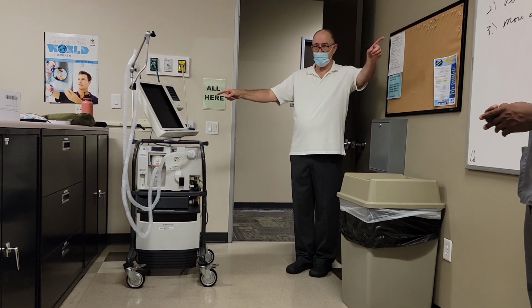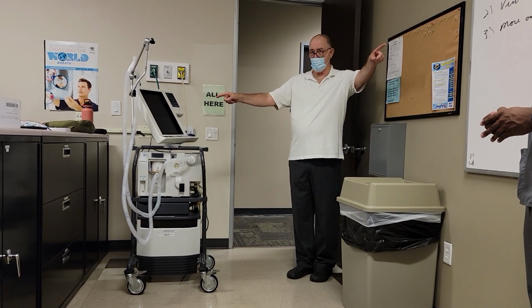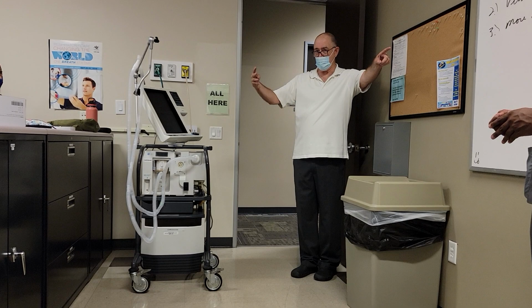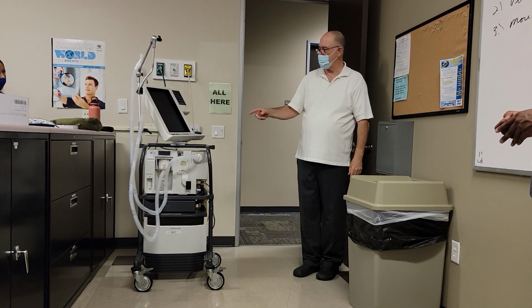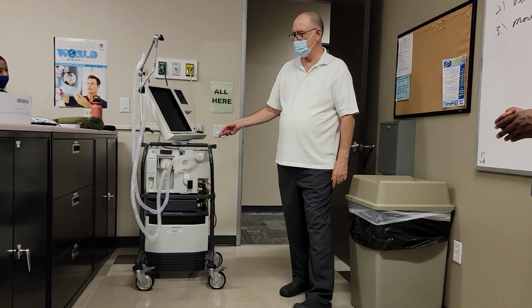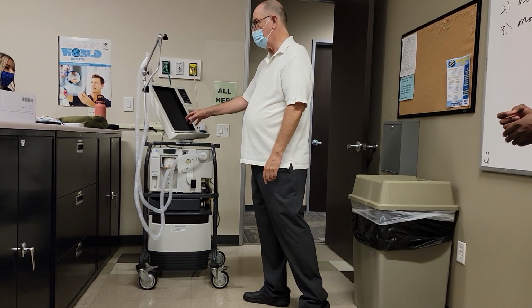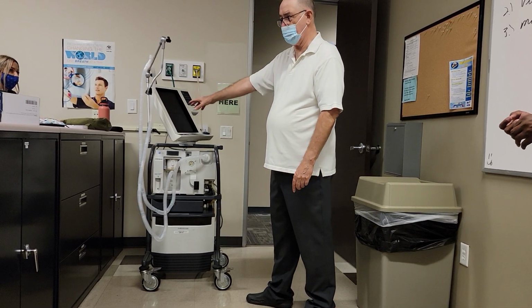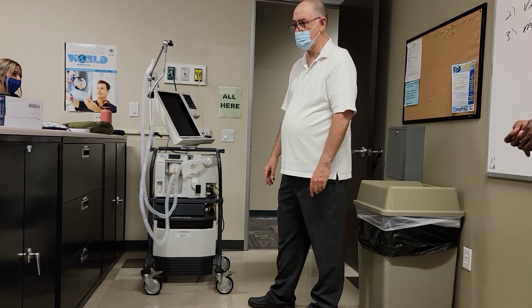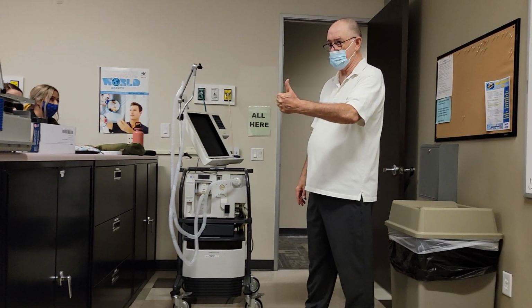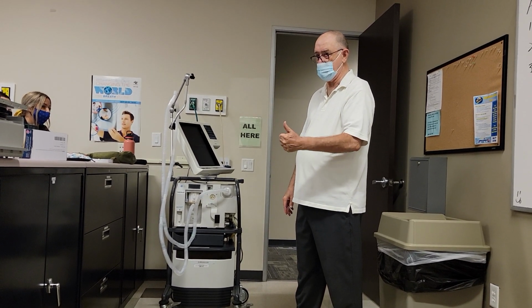And if you understand compliance and resistance and flow and time, those 4 variables, you can sometimes look at the patient, walk around the bed, get over to the ventilator, and you have assessed the patient and the ventilator, and you know what the problem is. Okay, I can guarantee you. Okay, it is a real skill. Okay.